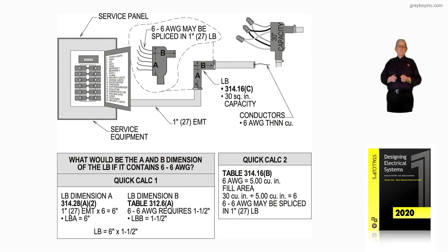Now, this illustration deals with LBs, and notice that in the quick calc, what would be the A and B dimension of an LB if it contains six number six AWG conductors? We can splice in an LB if it's listed to do so. If not, you're not supposed to make any kind of splice in an LB, just pull through it as a junction point.